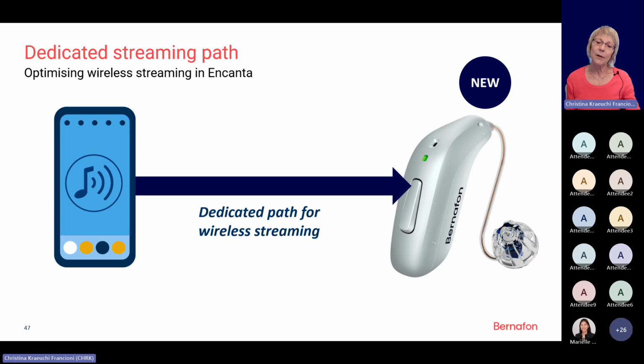Previously, all inputs which were not the microphone inputs were grouped together under an auxiliary path. This auxiliary path combined inputs from telecoil input, direct audio input, and wireless streaming. Now, mixing the auxiliary and stream signal with the microphone together could potentially mean that the streamed signal might be affected or interrupted when very loud sounds are picked up by the microphone. Consequently, the presence of these very loud sounds would attenuate the hearing aid gain, and it could also attenuate the level of the streamed signal. On rare occasions, this attenuation of the signal could potentially be noticed by the hearing aid user.